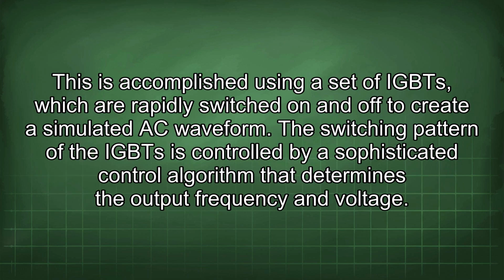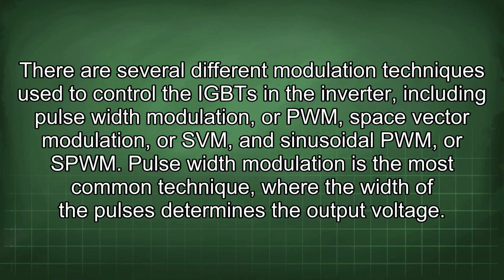This is accomplished using a set of IGBTs which are rapidly switched on and off to create a simulated AC waveform. The switching pattern of the IGBTs is controlled by a sophisticated control algorithm that determines the output frequency and voltage. There are several different modulation techniques used to control the IGBTs in the inverter, including pulse width modulation, or PWM, space vector modulation, or SVM, and sinusoidal PWM, or SPWM.